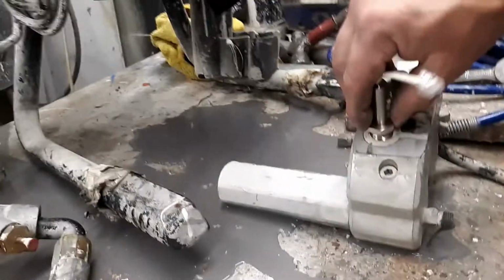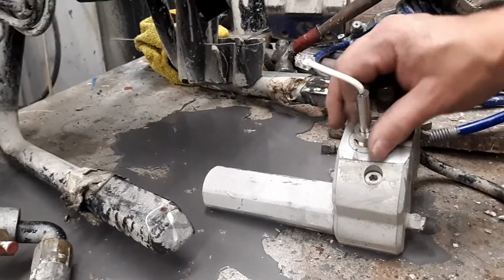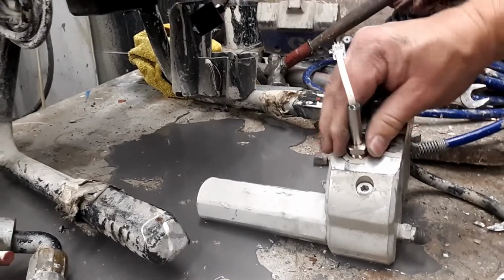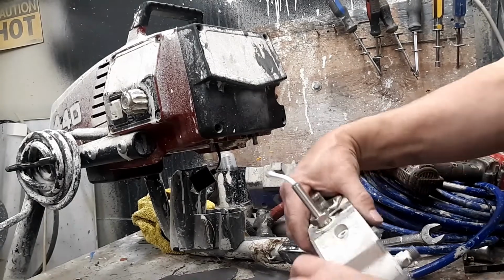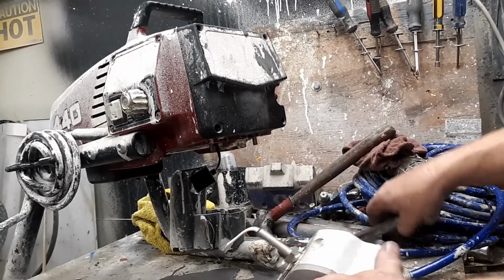So now all we do is put this back in. Don't cross thread it — the block is aluminum, and the transducer is stainless. If you try to force it, you're going to damage the block, and then you're going to be buying a new block.